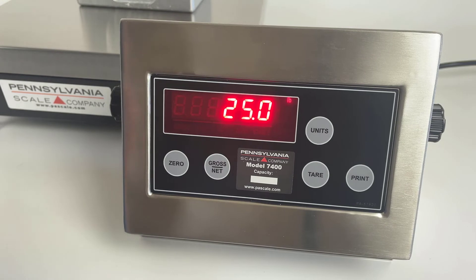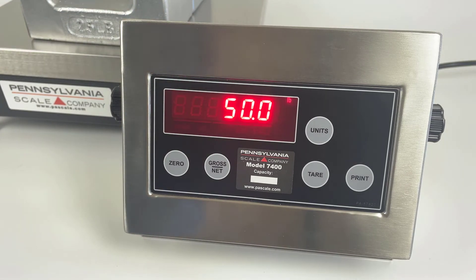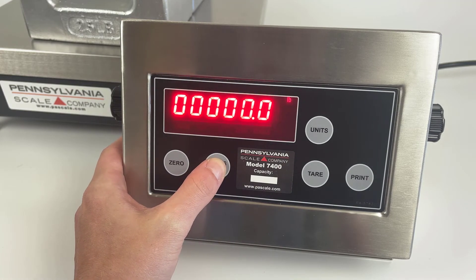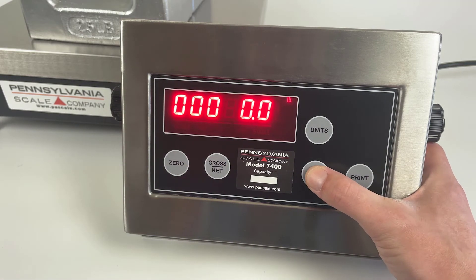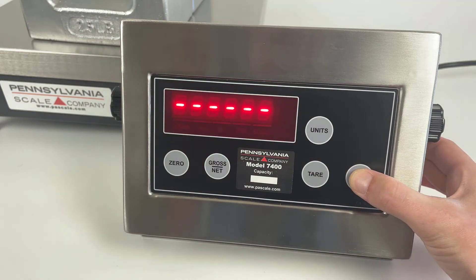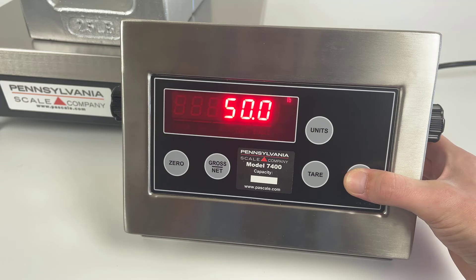Next, you can add more weight to the scale and again use the gross net key and tare key to input the value of the weight you've placed on the scale. Pressing print then calibrates.